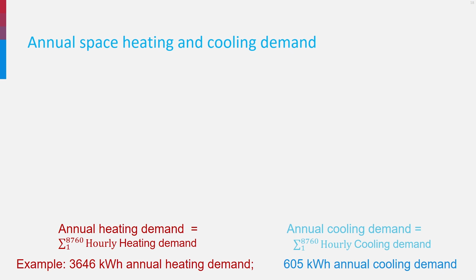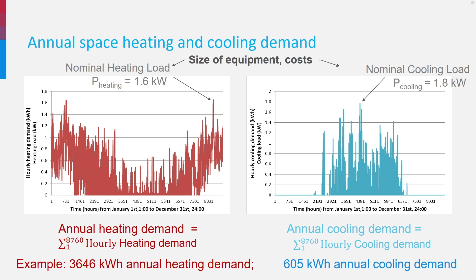Most important, you also see on the graphic the nominal heating load, also called nominal power. It is the maximum power the equipment should be able to deliver. For the heating, on the left, you see this peak at the end of the year in winter. The peak is 1.6 kilowatt that should be delivered by the heating equipment. For the cooling, on the right, you see that the maximum power is achieved in the summer and is 1.8 kilowatt that should be delivered by the cooling equipment. The price of equipment depends on this nominal load in kilowatt. The energy bills of the residents depend on the annual energy demand in kilowatt hour.